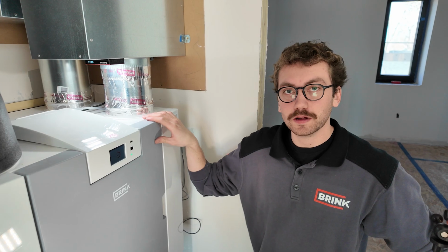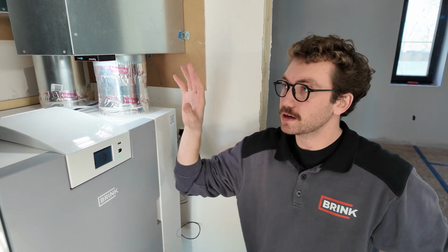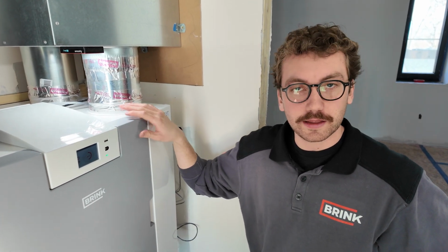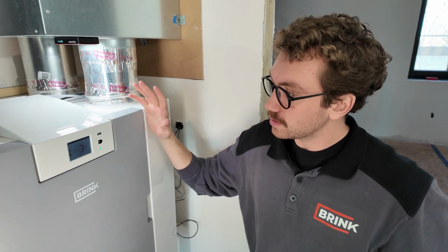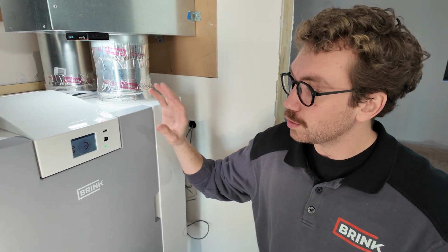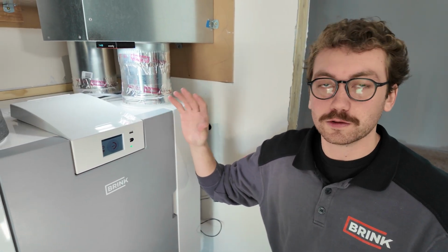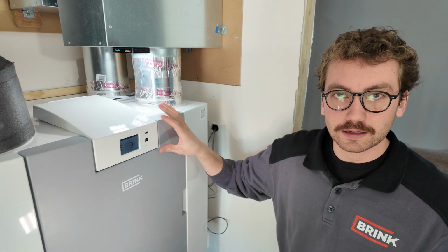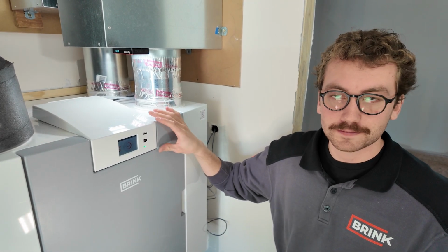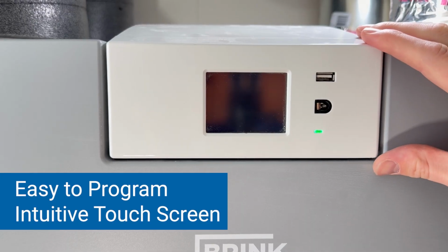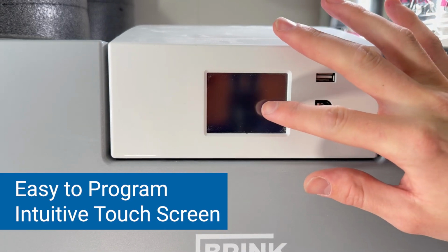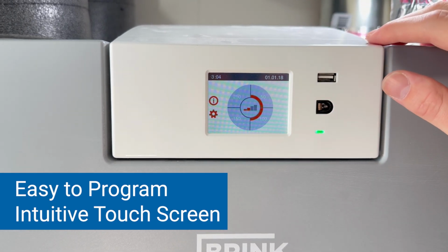So the unit is now plugged in. We've verified that all the ducting has been installed correctly and that everything looks good. The unit turned on okay. There are no error codes, so we're ready to start programming it. We'll start with the date and time, and then we'll get into the flow rates and any controls. So when you get to the FLAIR unit, the screen is going to be off. All you have to do is tap it, and it comes on.